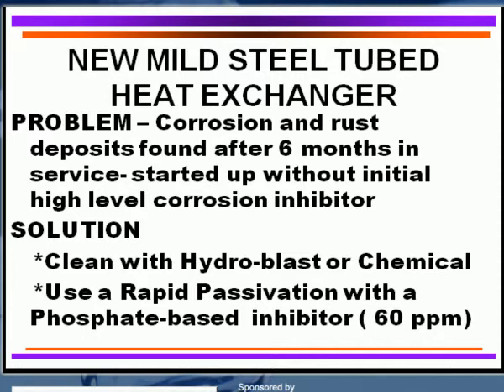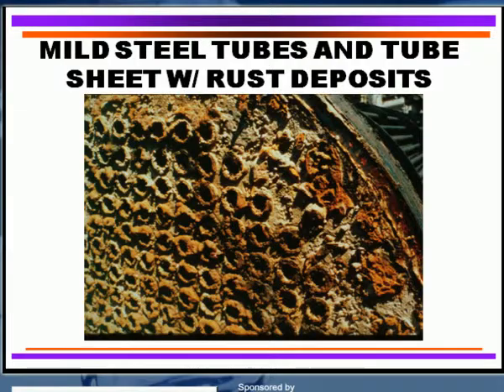So the key here for new heat exchangers, particularly mild steel, is to clean with either hydroblast or chemical cleaning if needed. If it's very new, maybe just a surfactant to remove oils and greases from fabrication. Then use a high rapid passivation treatment — a high dosage level of phosphate, usually around 60 parts per million for the entire cooling water system — and carry that for about a week to establish good protection on the metal surfaces.